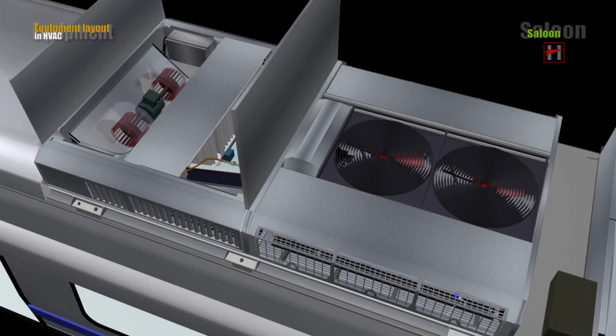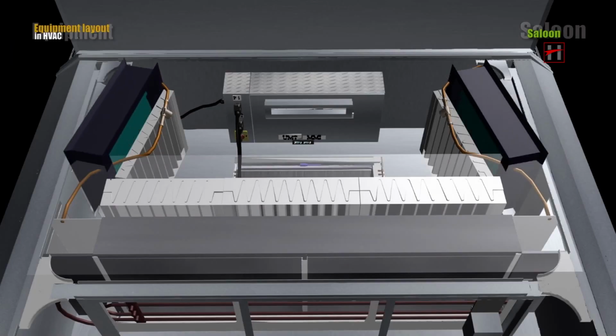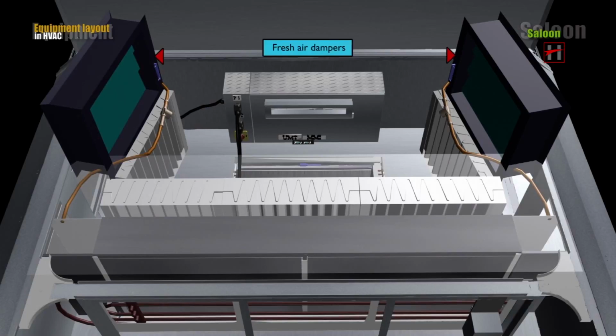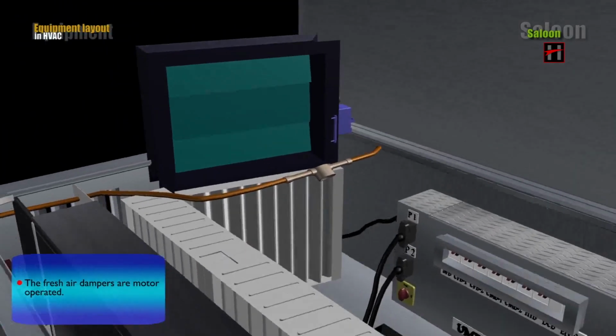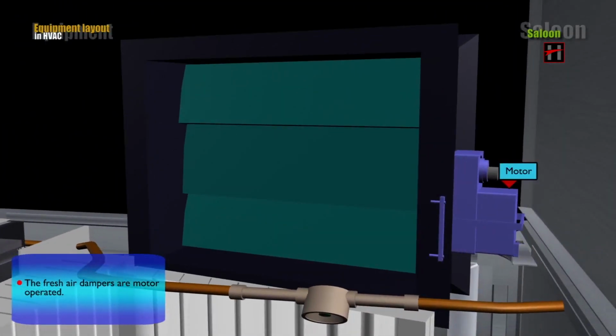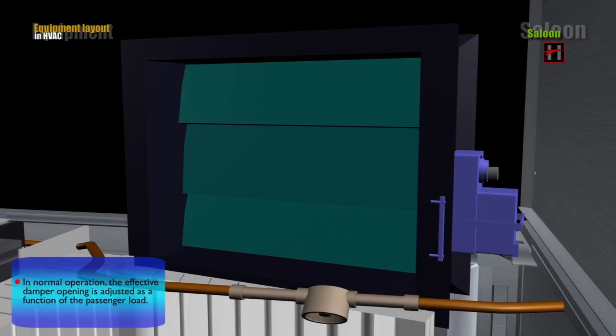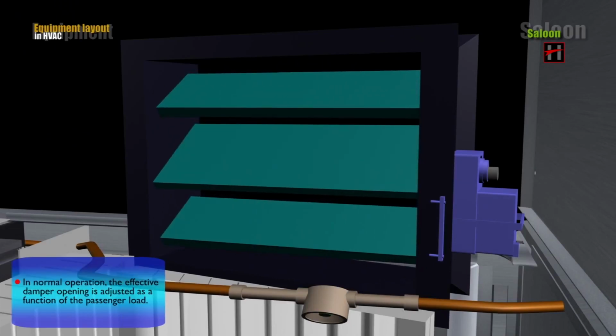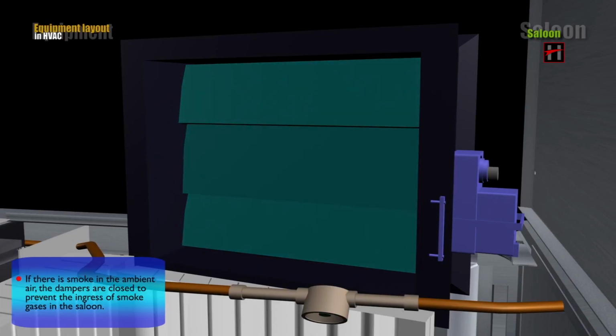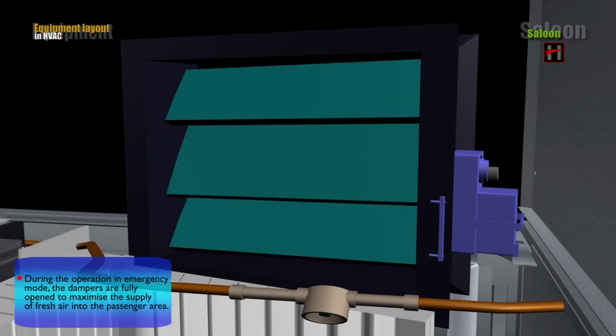Many serviceable components are located in the mixed air compartment. The fresh air dampers are placed on both sides of the mixed air chamber. The fresh air dampers are motor operated. In normal operation, the effective damper opening is adjusted as a function of the passenger load. If there is smoke in the ambient air, the dampers are closed to prevent the ingress of smoke gases in the saloon. During the operation in emergency mode, the dampers are fully opened to maximize the supply of fresh air into the passenger area.